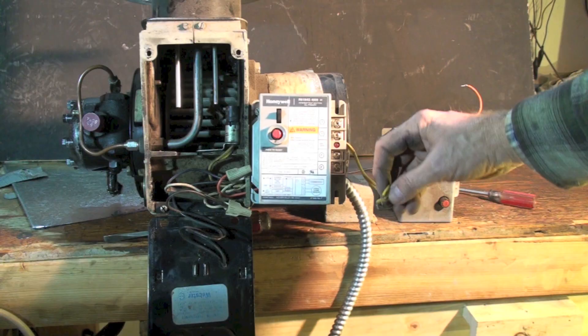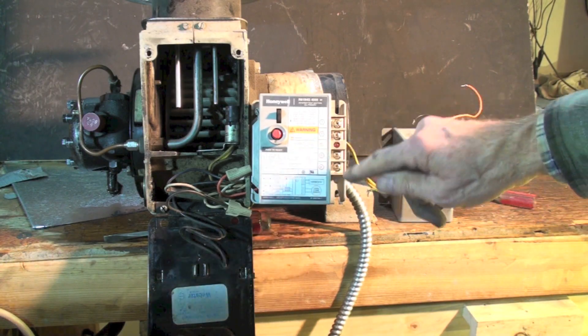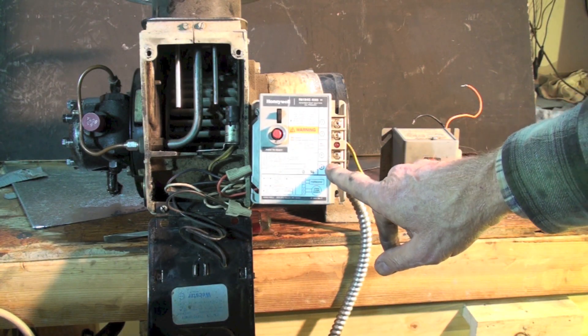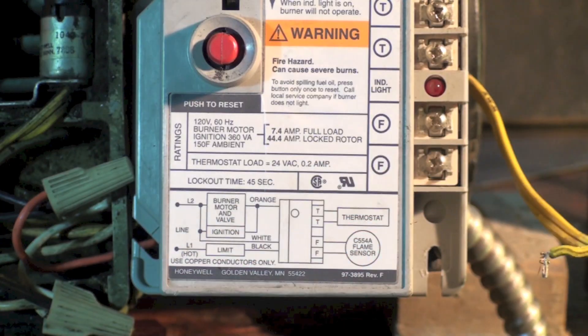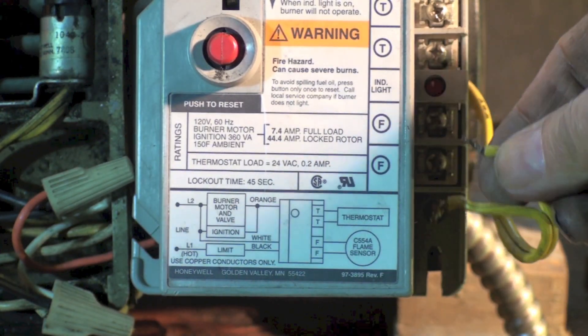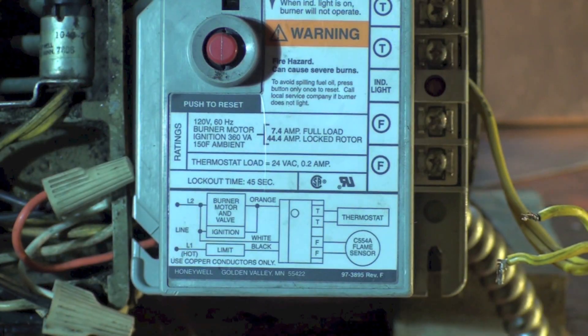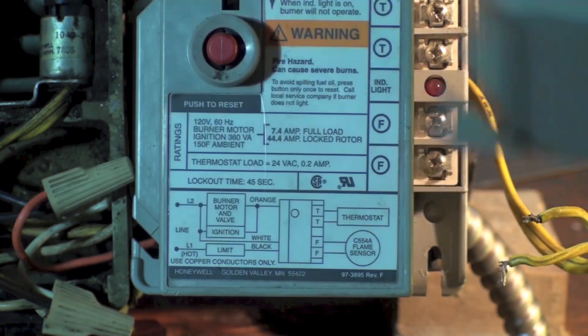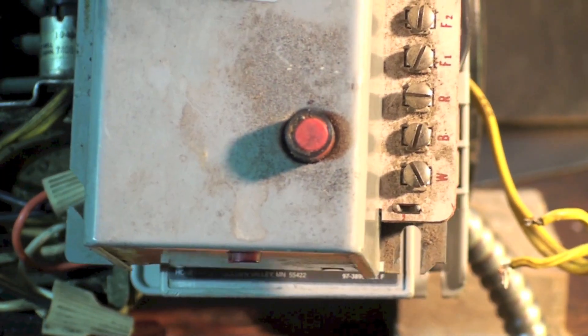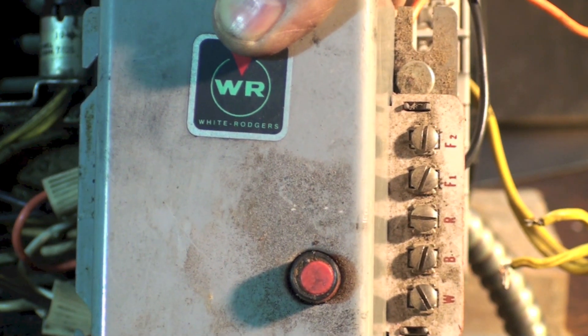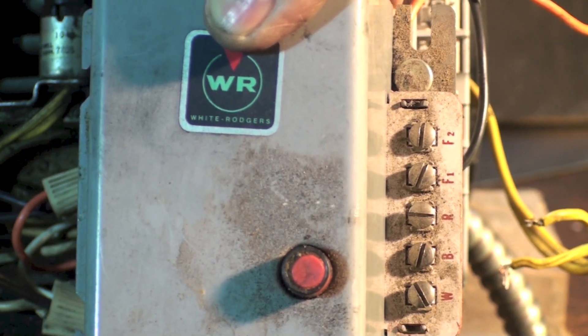The only other wiring you have to do is, on the Honeywell, it's the FF, and that's these yellow wires that are coming from the cad cell itself. And here again, on the White Rodgers, it's F1 and F2, and it doesn't make any difference which wire goes where.